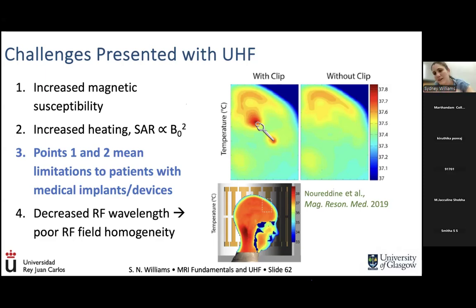However, if you look at the color bar, the amount of heating relative to none is still quite minimal. It's at most maybe 0.3, 0.4 degrees Celsius, so that's quite within an acceptable range. And when you go out to the larger scale view of the brain, you can see that in reality this clip is not affecting the overall temperature change in the brain greatly. So in this case, this would be an acceptable device or implant for scanning at ultra high field. But unfortunately, that cannot be said about a lot of things yet. Because of the risk associated, it's a slow moving process to find ways to mitigate this and to gain more approval and consensus for scanning these types of implants and devices.